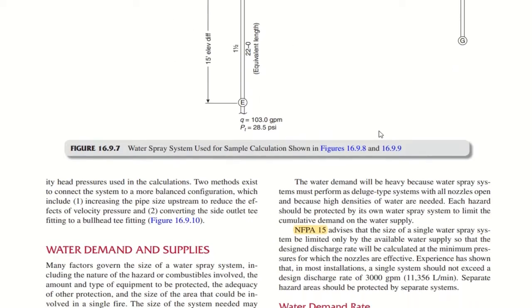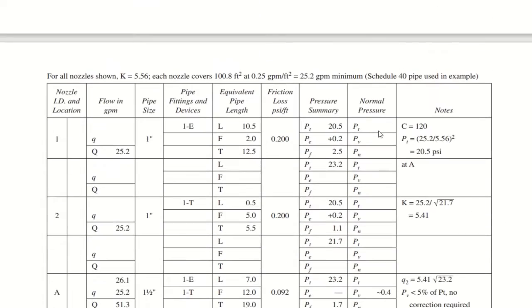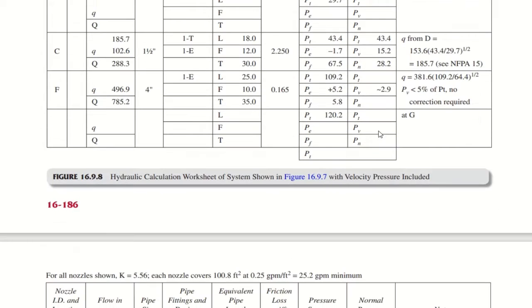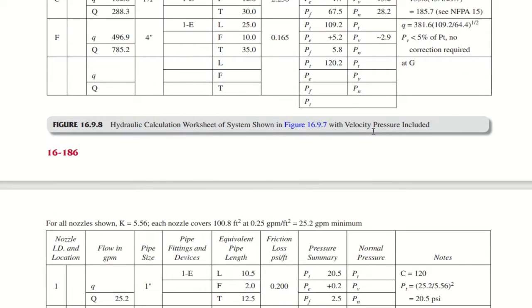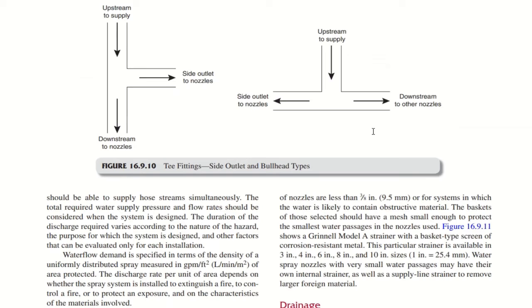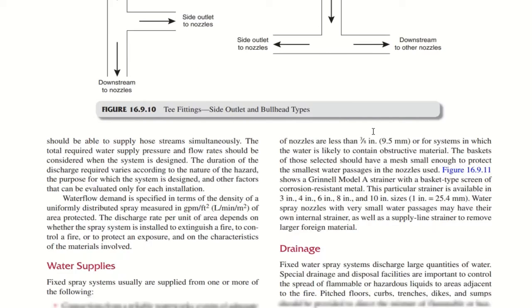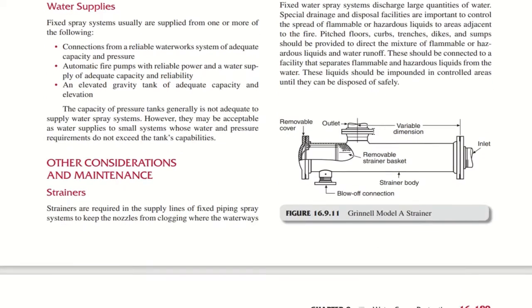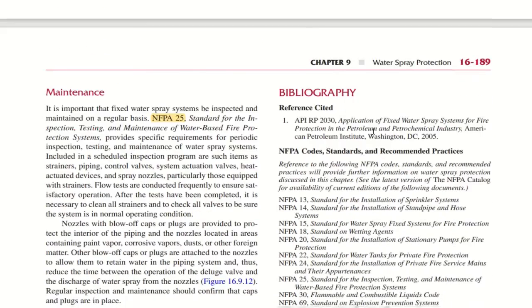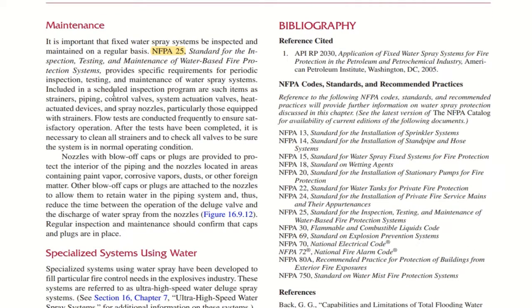So they have just given the sample calculation here. This table is also related to the hydraulic calculation for water spray system. So tees, fittings and so on they have shown. Other maintenance considerations they have shown. It is important that fixed water spray systems shall be inspected and maintained on a regular basis. NFPA 25, the standard for the inspection, testing and maintenance of water based fire protection systems, provides specific requirements for periodic inspection, testing and maintenance of water spray systems.